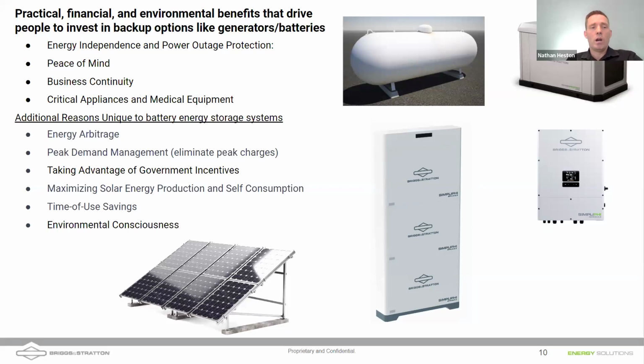You can also, of course, pair an energy storage system with renewable energy resources. Typically you have a capital investment, but then you can get that energy for free, like a solar array, right? And so with a solar array, with energy arbitrage, your inverter and battery system can pay for itself over time, right? That's a difference to using a generator with some fuel system, is that the generator doesn't pay for itself over time. Not that that's a bad thing. That peace of mind might be worth it to have that generator, and you get very long run times out of a generator. But there are also government incentives that you can take advantage of when you're installing an energy storage system. And so keep those in mind.